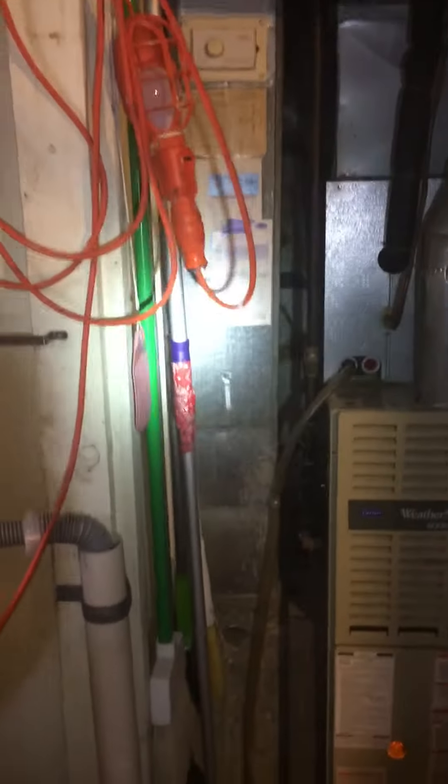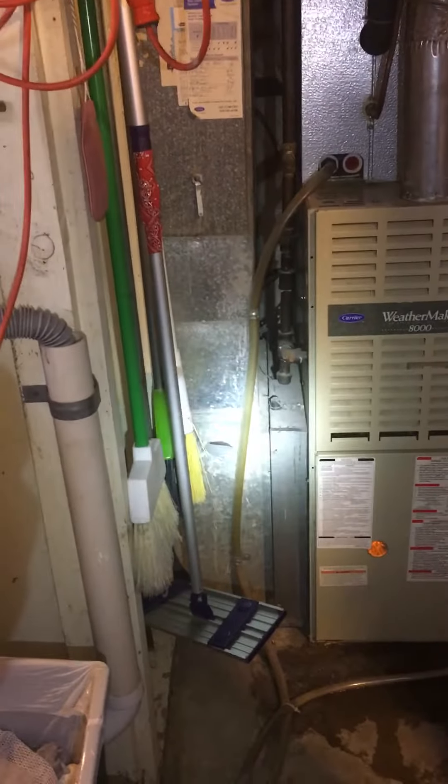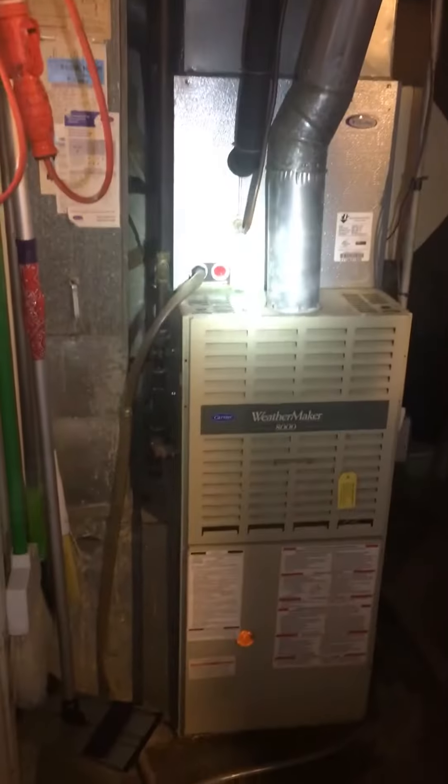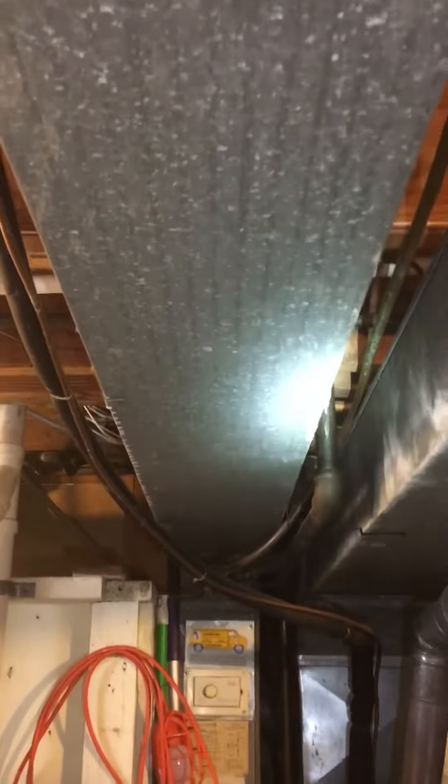The floor drain is right in front of us. The ductwork return air drop is 8 inch by 22. They want to look at making a bigger return air drop — we don't have a whole lot of room between the furnaces; got dimensions on that, may have to shift the furnace over a bit if they go with a whole new system. We'd get a new air cleaner in there, and the return is only 9.5 by 8 going each way, so we'll look into that.